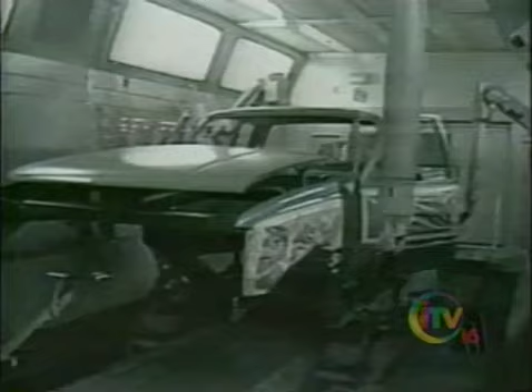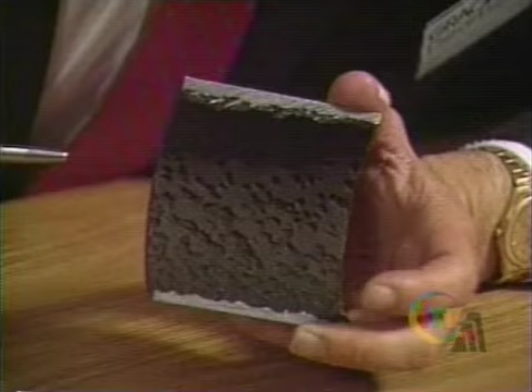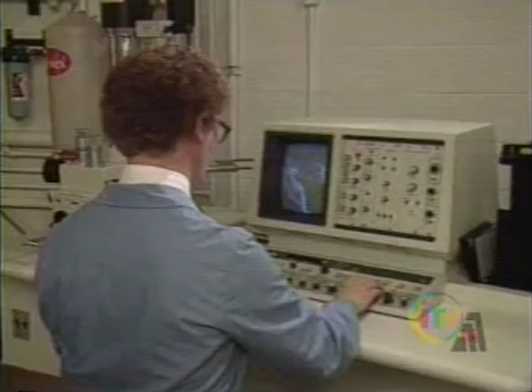Dr. Jack Kelly of the W.R. Grace Company studies ways to reduce boiler tube corrosion. This is extremely serious because if you do have pitting attack, you lose metal, and there's no chemical treatment that I'm aware of in which you can replace the metal. Eventually, this pipe failed and had to be replaced. In this case, the primary corrosion process involves oxygen interacting at the surface with iron ions, oxidizing it and removing it from the surface.